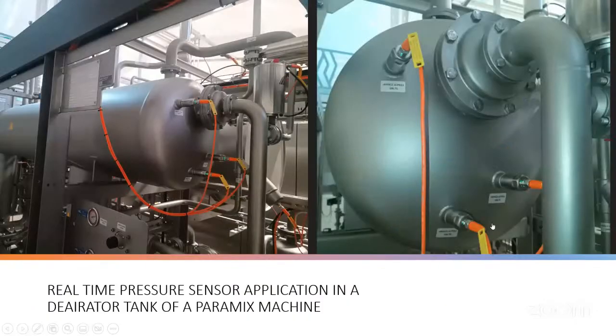And these are examples of physical sensors. You can see an example of a physical sensor here used as a pressure sensor in the industry. This is a very good example. This is a deaeration tank and how sensors are being applied. You can see they are connected directly with cable, which goes over to the input card and then transmits the information, like I said before, to the programmable logic controllers. So from here, the hydrostatic pressure gotten from the sensors themselves is transmitted to the programmable logic controller. The logic controller itself acts on the information transmitted by the sensor.